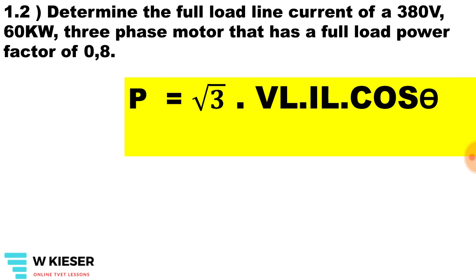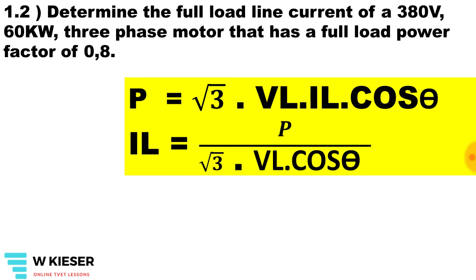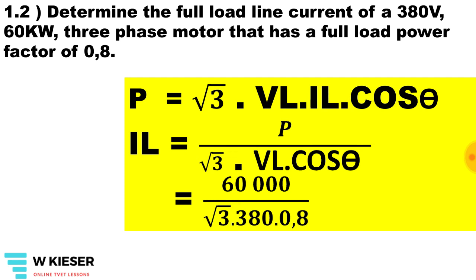Determine the full load line current of a 380 volt, 60 kilowatt three-phase motor that has a full load power factor of 0.8. Because it's a three-phase motor we're dealing with square root 3 inside our equation. To manipulate the equation to get the full load current on its own, it'll be power over square root 3, the line voltage, and the power factor. The power multiplied by 1000 gives us 60,000 watts divided by square root 3, the line voltage of 380, and a power factor of 0.8. Therefore the full load current is 113.95 amps.